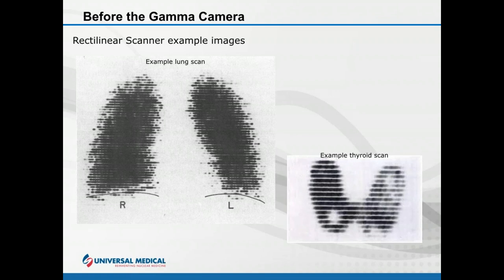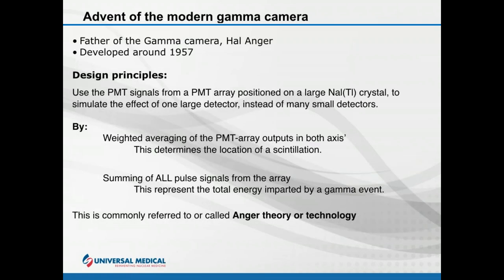In about 1957, Dr. Hal Anger developed the principles of the modern gamma camera. What Dr. Anger came up with was using PMT signals — photomultiplier signals — from an array of multiple photomultipliers positioned on a large sodium iodide crystal. The purpose is to create one large detecting element instead of many small ones. A weighted averaging of the PMT array outputs determines scintillation location, and the summation of all PMT outputs determines gamma energy. This is often called Anger theory or Anger technology.